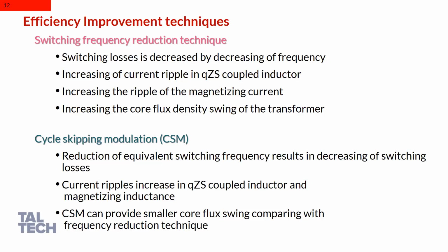In the case of cycle skipping modulation, this technique has a good effect on reduction of switching losses, but current ripples in coupled inductors and magnetizing inductance are increased. However, the effect of cycle skipping modulation on core losses and core flux density, compared with frequency reduction, is low, and it has a smaller effect on core flux density.